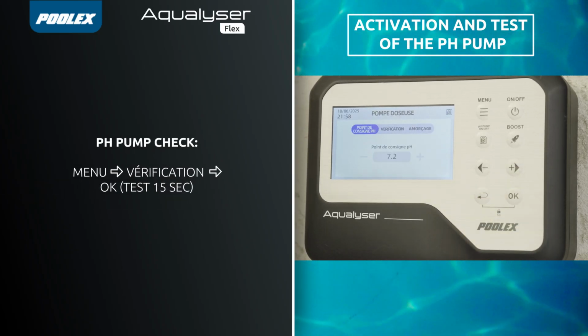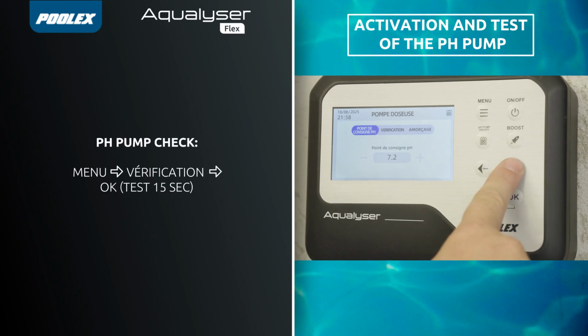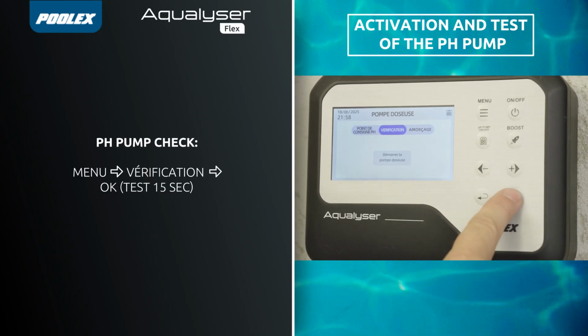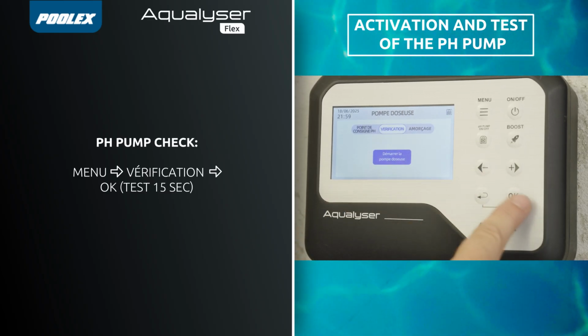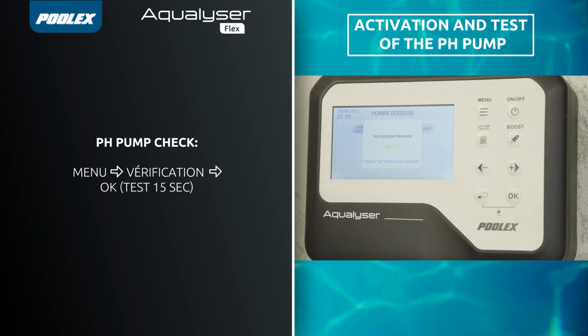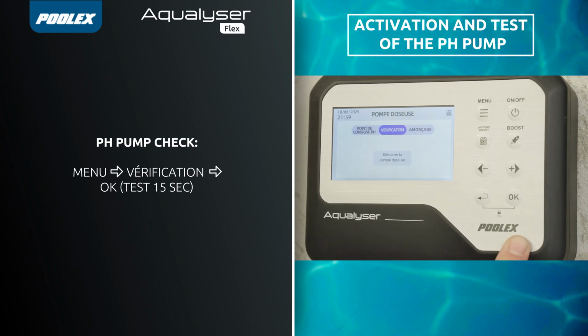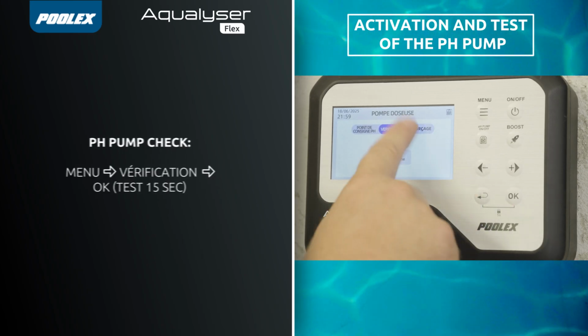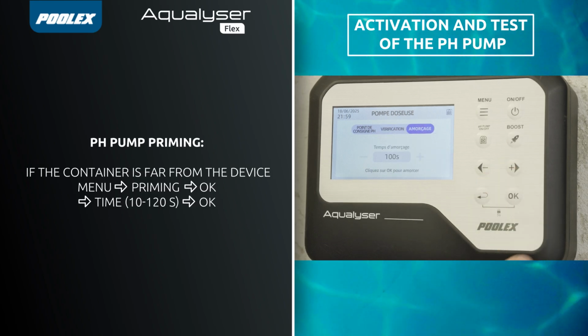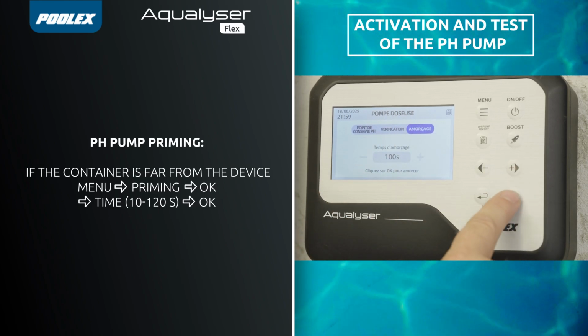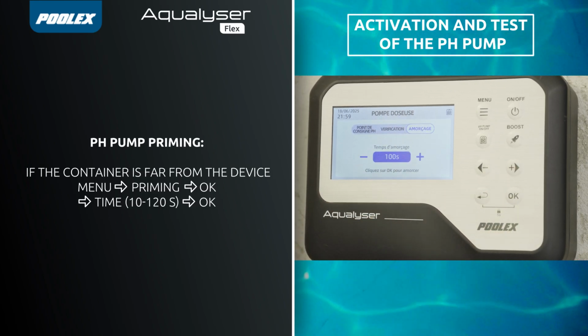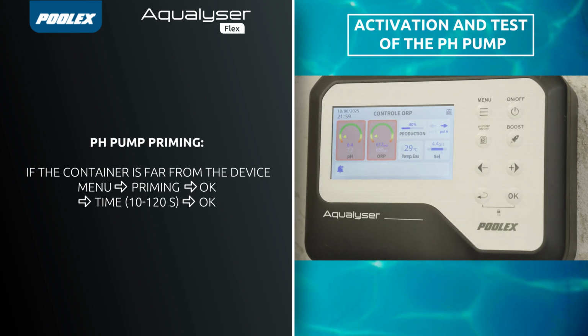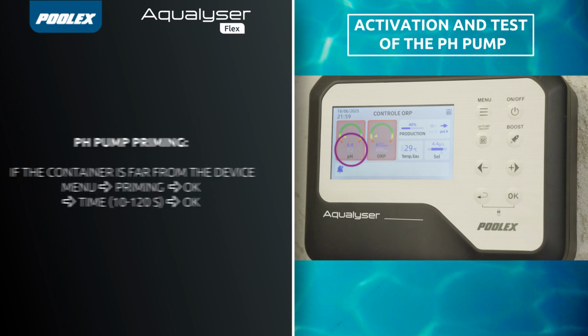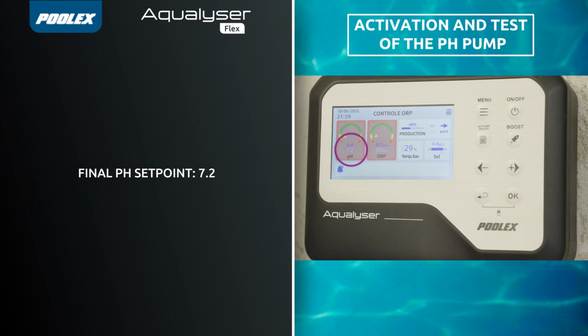To check pump operation, use the arrows to go to Verification and launch the 15-second test with OK. If necessary, prime the pump by selecting Priming, then confirm with OK. Depending on the distance between the pH pump and the container, you can set the priming time between 10 and 120 seconds. Finally, check that the pH set point is correctly set to 7.2.